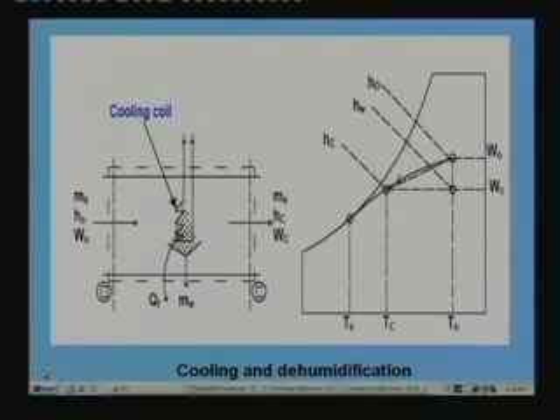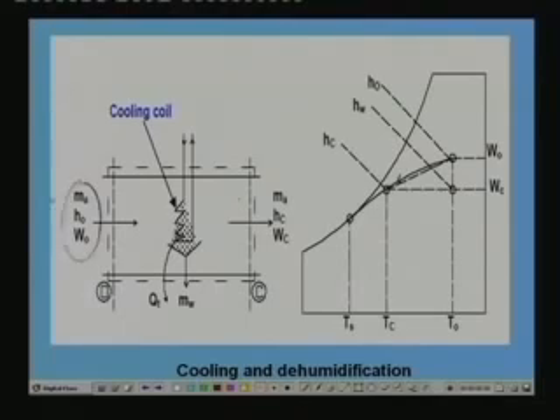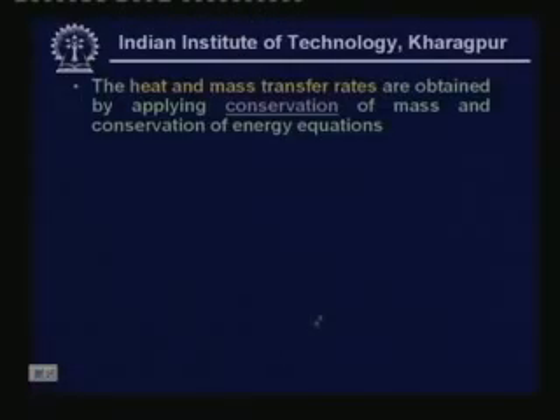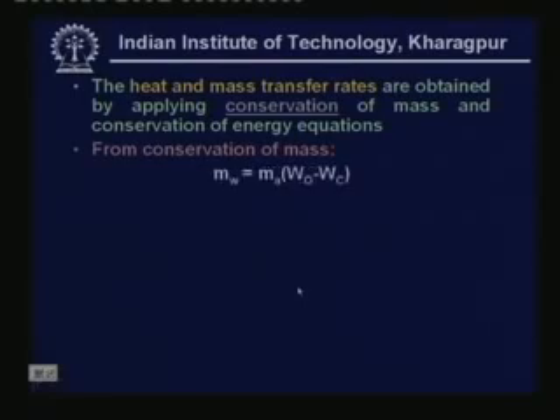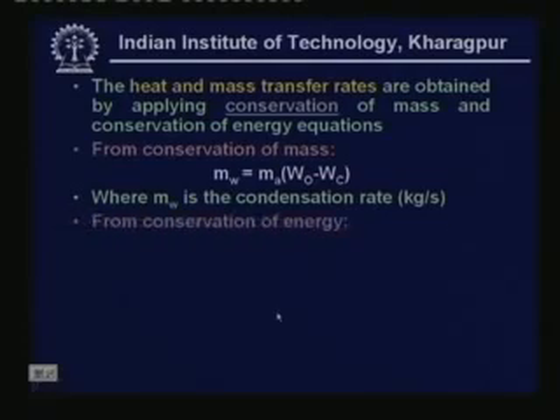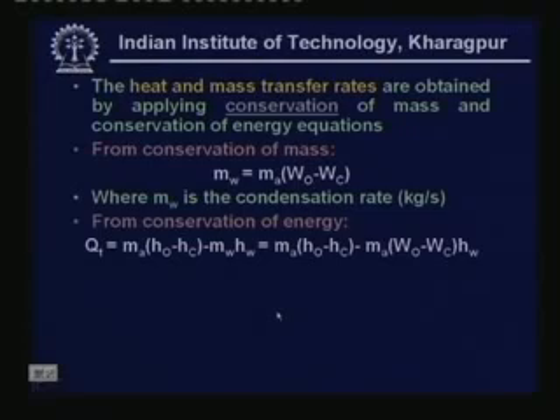Similarly, one can write the energy balance, take the control volume, and for steady state whatever energy is coming in must go out, and energy coming in is in the form of enthalpy of the air, energy leaving is also in the form of enthalpy of air, and also there is some energy leaving by enthalpy of condensate, and some energy has to leave because that is nothing but the load on the cooling coil. So as I said, from conservation of mass we can show that m dot W is equal to m dot A into W naught minus Wc, where m dot W is the condensation rate in kg per second. So many kgs of water is being condensed per second, that is the meaning of this. And from conservation of energy we can easily show that the load on the cooling coil Qt is equal to m dot A into H naught minus Hc minus m dot W Hw, and for m dot W we substitute using the conservation of mass. So finally we find that Qt is equal to m dot A into H naught minus Hc minus m dot A into W naught minus Wc into Hw.